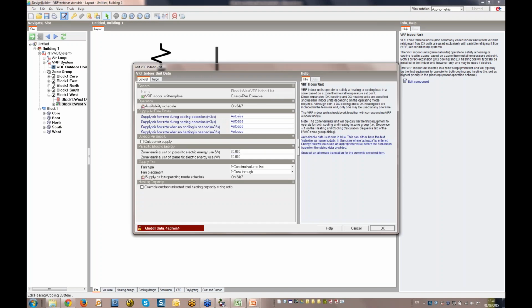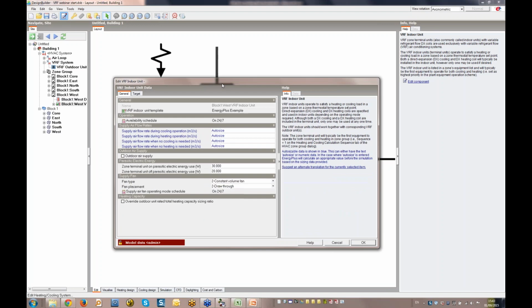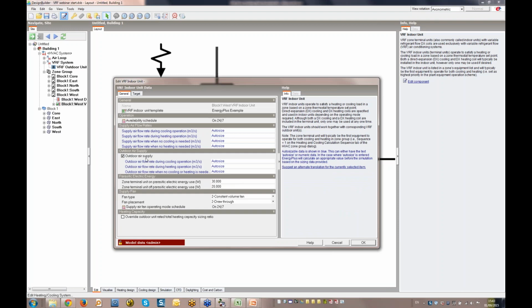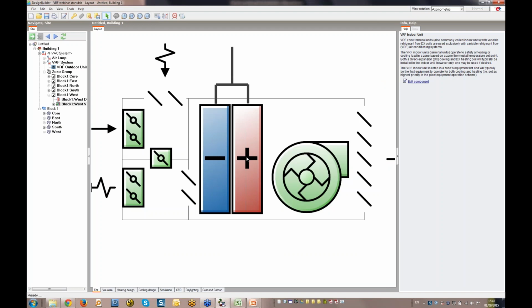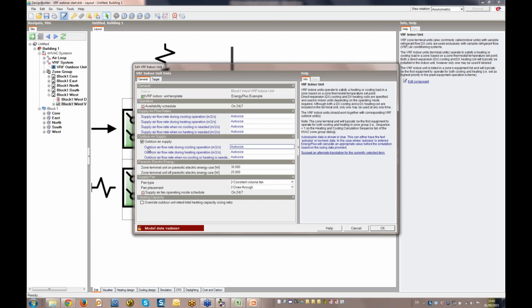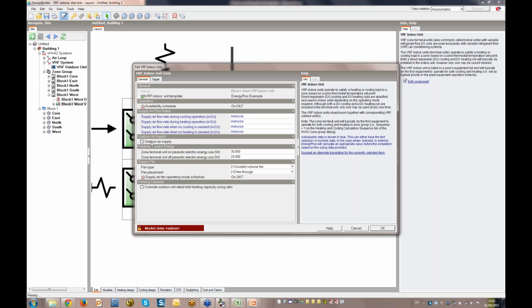Here you can see the various options available for the whole terminal unit, which again is fully auto-sizable. Here's the option to specify a direct connected outdoor air supply. This is now clearly shown in the schematic. This option has very limited control and no airside heat recovery. A DOAS system, as we're using here, is much more efficient and controllable, so is generally preferable to this direct air option.